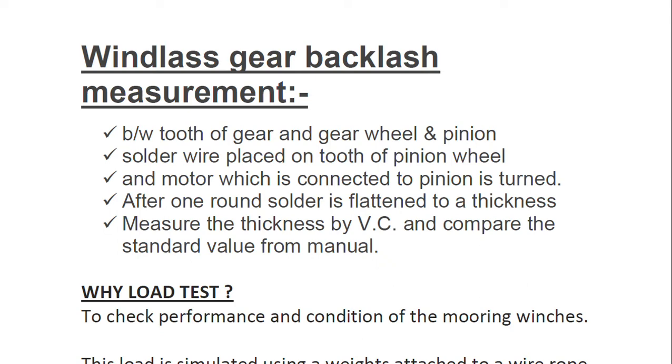We use a solder wire, which is placed between the tooth of the pinion wheel. The motor, which is connected to the pinion, is turned one complete revolution. Because of this, the solder wire becomes flattened — it is circular and cylindrical in shape in 3D. After turning a full revolution, we take it out and measure it with a vernier caliper.